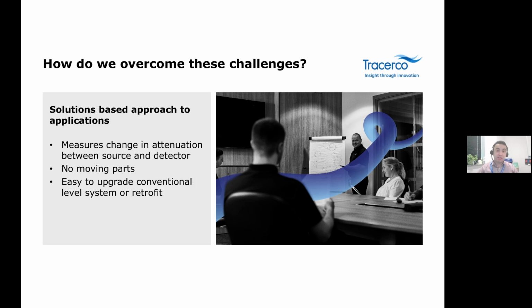The size and activity of the source is calculated based on the vessel design, such as the wall thickness and insulation, and the process content. There are variations depending on the application, which enable you to measure more than just the bulk level, in the form of interface and density, or a mix of all three in more advanced instrumentation.